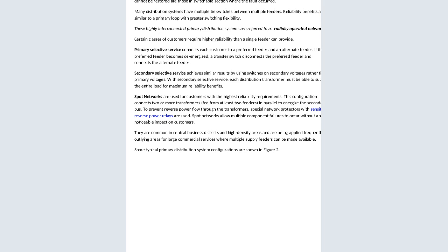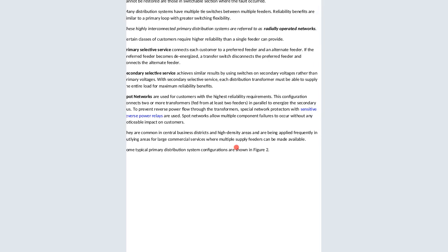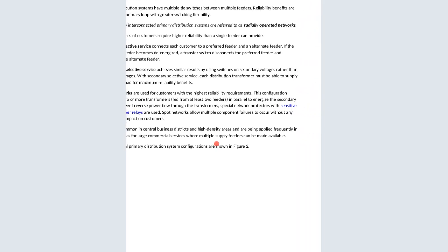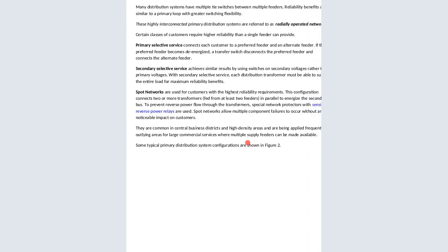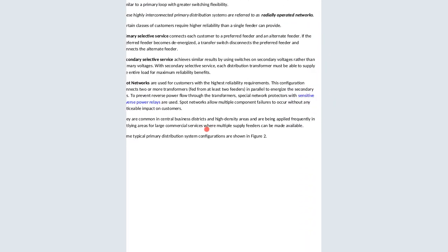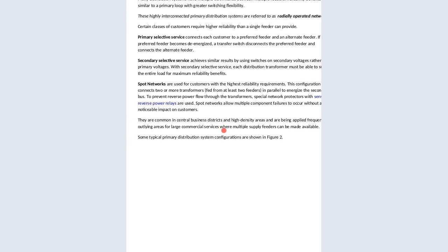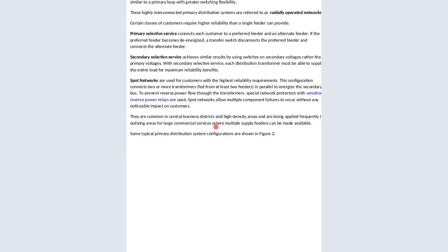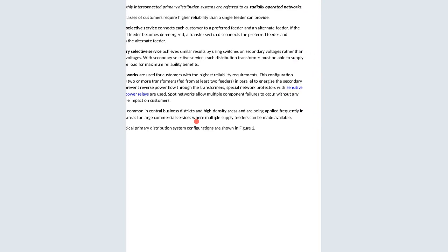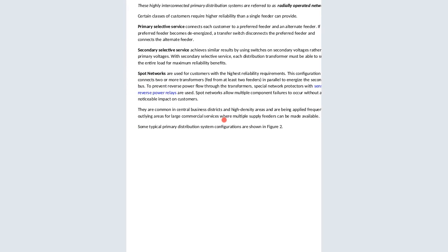Other types of networks are called spot networks. They are used for customers with the highest reliability requirements. That is, this configuration connects two or more transformers, fed from at least two feeders, in parallel to energize the secondary bus. To prevent reverse power flow through the transformers, special network protectors with sensitive reverse power relays are used. So the spot networks allow multiple component failures to occur without any noticeable impact to customers. So these are highly reliable customers.